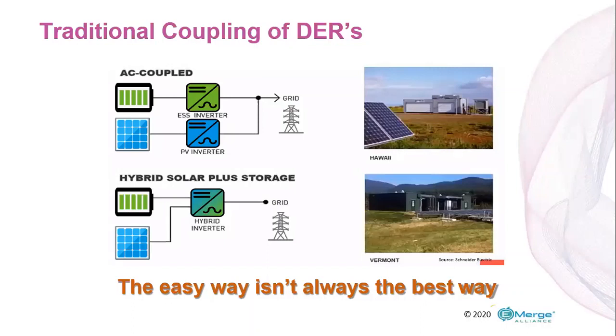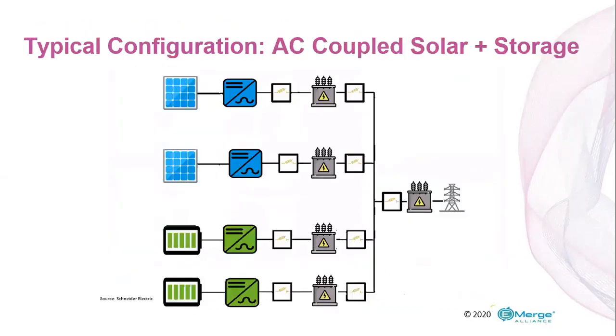But as time went on, a couple of different things happened in the inverter technology area to expand capability here. One was to have inverters that could take in both the PV, which needed to be managed in a different way than batteries did, but in a common inverter, providing again the linkage back to the grid. Generally speaking, when you're AC coupled, you then have to put in a disconnect of some sort to the grid if you want to use that power locally.